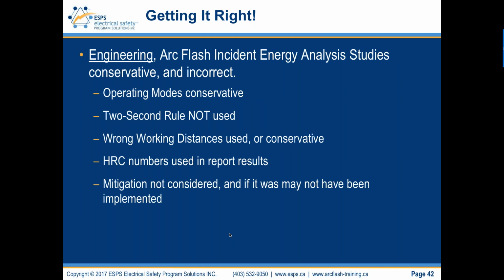So engineering studies, the problem with these studies is I find that, you know, and they're getting better, but initially the engineers were learning, which is fine, but I don't think some of the engineers have evolved to realize that their previous studies were incorrect or that they didn't make the right assumptions. So operating modes are conservative. The 2-second rule is not used, or the 2-second guideline in IEEE 1584. The wrong working distances are used, or conservatively, the engineer used 18 inches for everything, both low and high voltage. HRC numbers used in report results. Mitigation not considered, and if it was, may not have been implemented.